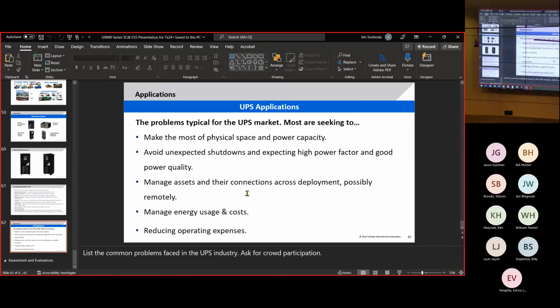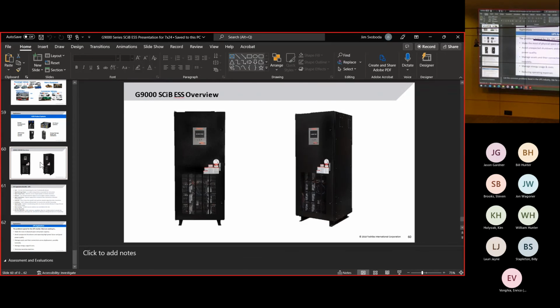Question: one of the pictures showed IP ports - would you hook up the monitoring straight to IP and aggregate that? Answer: that's correct. Each jar sends its data to a battery management system for the string or cabinet, and from there you can collect data from different cabinets into a host and send it over IP, or do it individually per cabinet. You get access to the actual data points for each cell. Follow-up: is that internet protocol or CAN bus? Answer: internally it's CAN bus, but reporting to the customer is over IP.